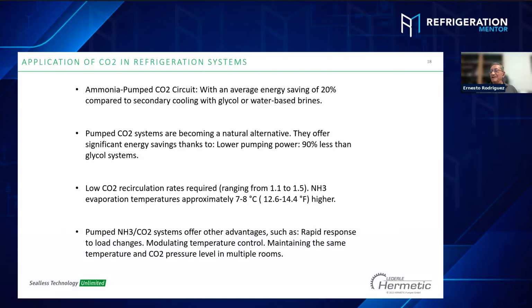What does recirculation mean? Basically, when the pump recirculates the flow to the heat exchanger, to the coil, it means you have 2 parts of liquid and 1 part of gas. The more you increase the flow of the pump, the more you increase this rate. It's going to be 3 parts of liquid and 1 part of gas.